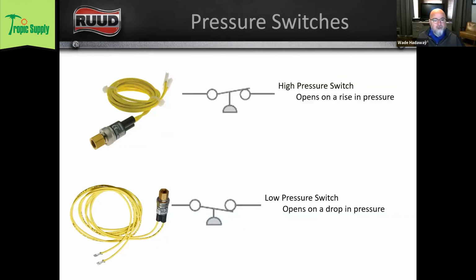Now, typically, the pressure switch itself will have some sort of writing or designation on that to tell you at what pressure that switch opens, and then again when it closes. It's the same for the low pressure. And you can see the pressure symbol is the same, but whether it opens on a rise or opens on a drop depends on how the actual contact or the switch itself is drawn, right? So the top switch opens on a rise in pressure, meaning as pressure pushes up, right? Pressure increases, that's going to push that switch open, is how I look at it. And on low pressure, as pressure drops, that symbol is going to pull that switch open.